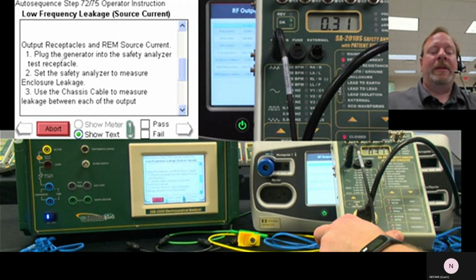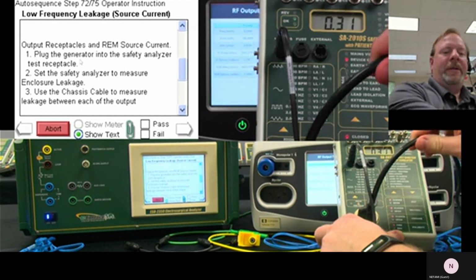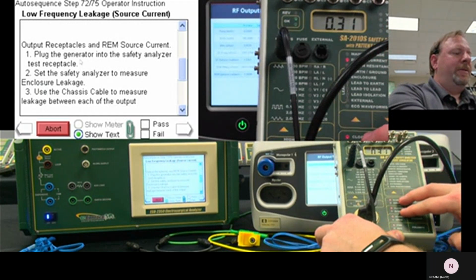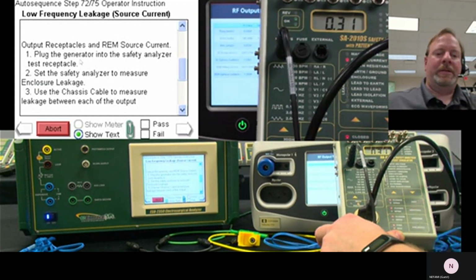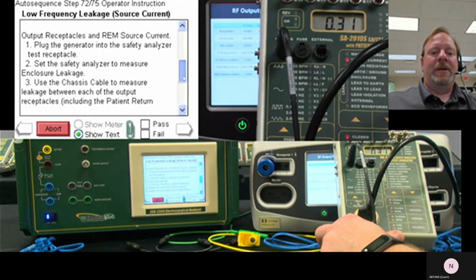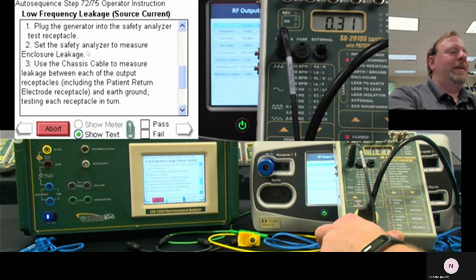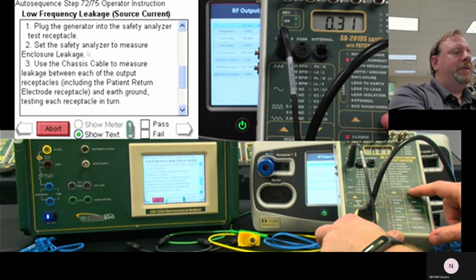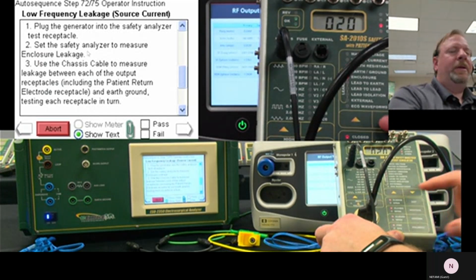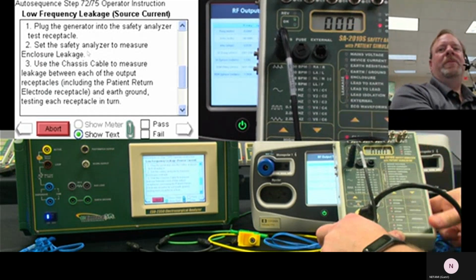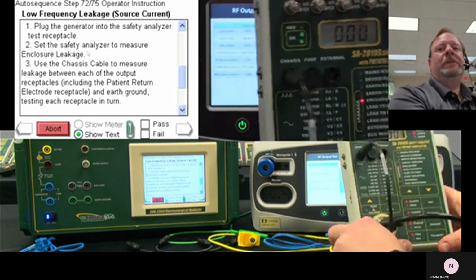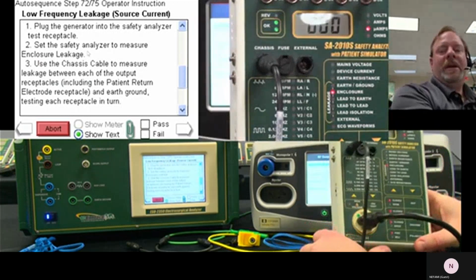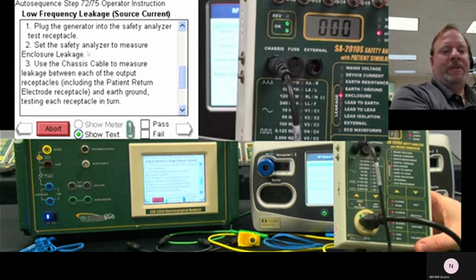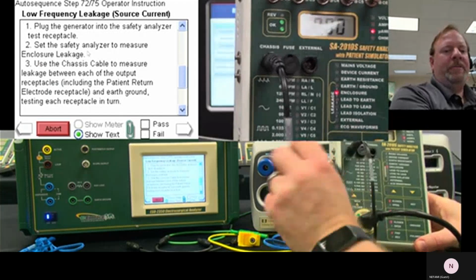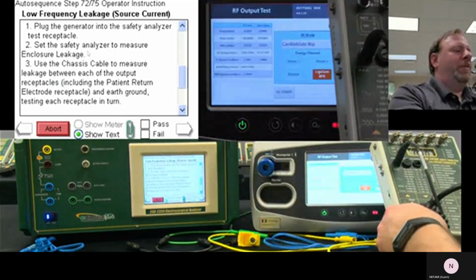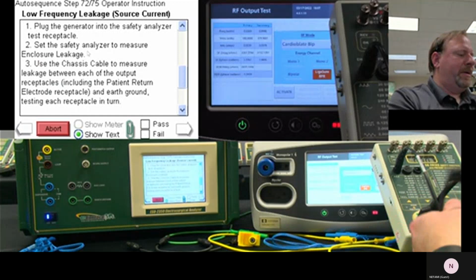But in this case, it's telling us exactly what to do. Plug the generator into the receptacle. Make sure the hot and neutral are closed. The connections are closed. So now the device is on. Set the safety analyzer to measure enclosure leakage. Enclosure leakage. I don't know how well that's visible on the screen there. Okay, enclosure leakage. And then use the chassis cable to measure between each of the output receptacles, including patient return. So in this case, what we're going to do is find the highest current that we can find.